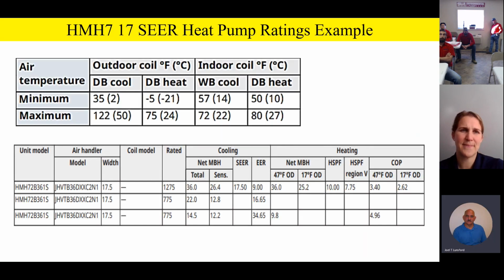The other thing we like to talk a little bit about on the unit as we move forward, with some of the ratings and stuff like that, is if you take a look at it, you're going to notice that the outdoor unit and the indoor coil have a pretty wide operating range from a minimum to a max. To give an example, for cooling you can actually go down to 35 degrees outside, up to 122 degrees. And in the heating mode of operation, this thing will operate down to -5 degrees outside, which is pretty nice. And maximum heating would be 75 degrees outside. So you can look at those charts a little bit.